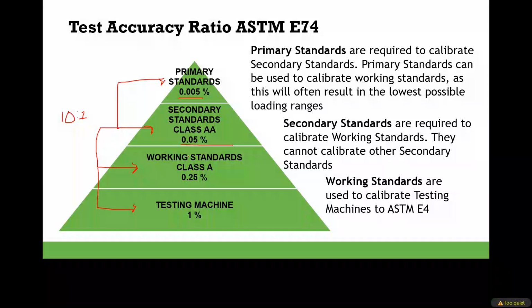By multiplying this lower limit factor by 2000, we're going to guarantee the first point is 0.05. And then the class AA, they have this multiplier that's 400 that I was talking about, which basically says, hey, I'm 5 to 1. And then that end result, when I go out and calibrate that testing machine, unless it's an Instron machine that's a 0.5%, then I'm 4 to 1. And there's ways, if you're doing an Instron machine, if you want to maintain the 4 to 1, you multiply by 800.